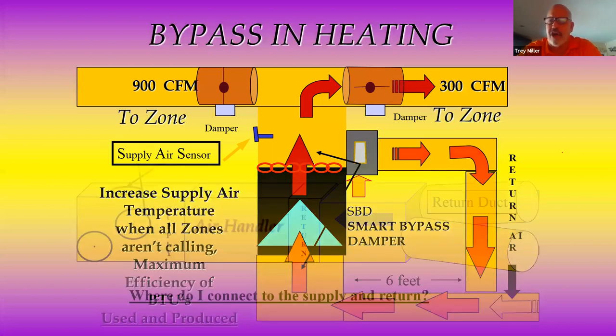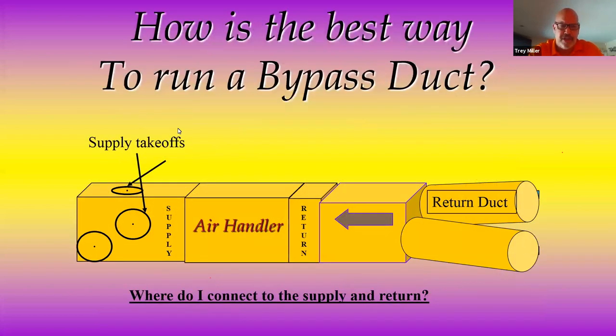Now, where do I install the bypass? First of all, gentlemen, this has got to be the first takeoff. There are no exceptions here. It has to be equal to or in front of all takeoffs. If you don't have it like that, then guess what we've done? We're not going to balance the system out. It's got to be equal to or in front of all takeoffs. That way we can balance it. But then where do we tie it into the return? That's been a problem for years.